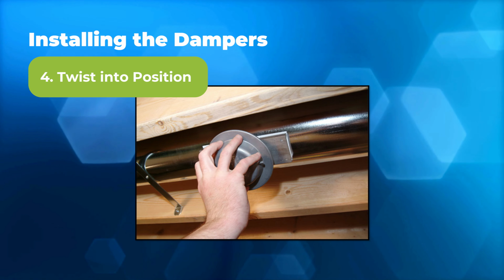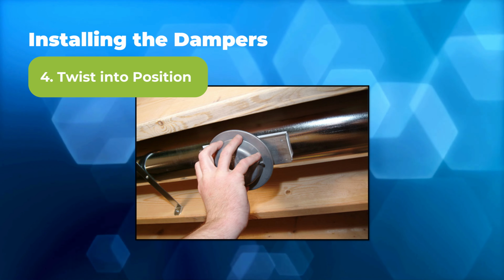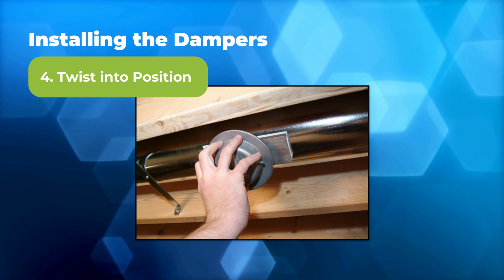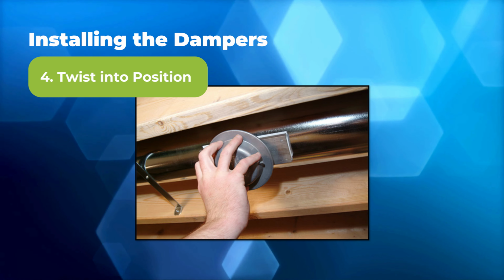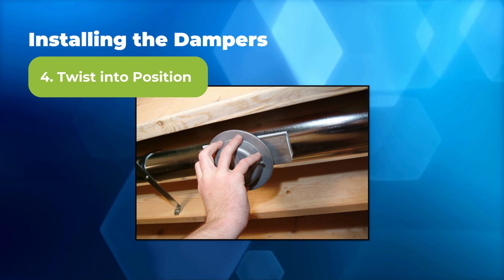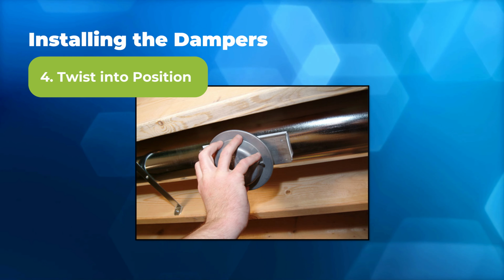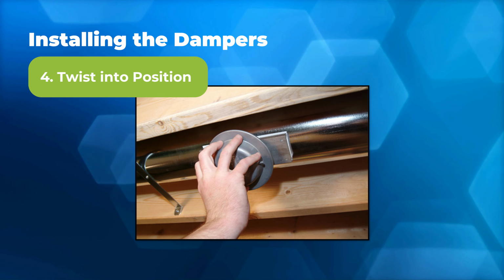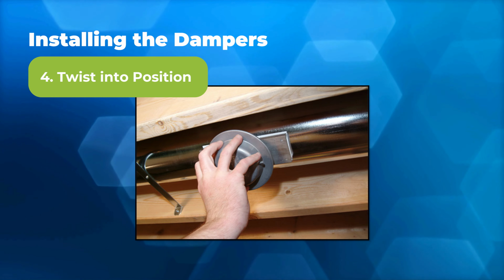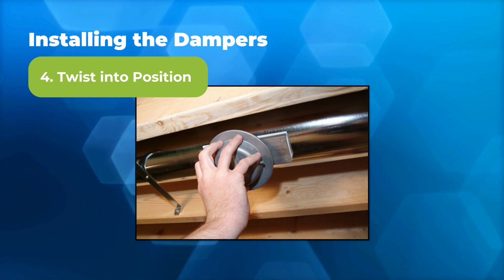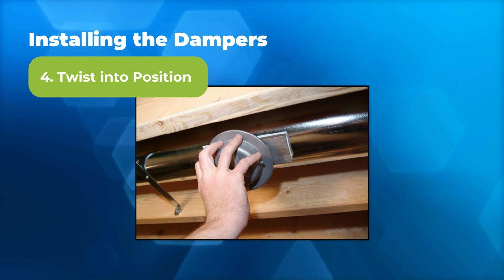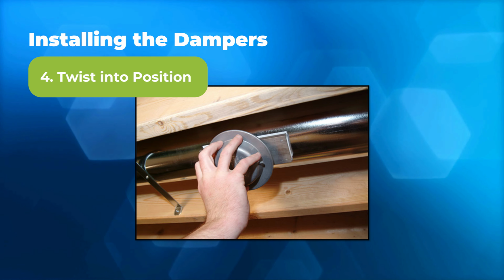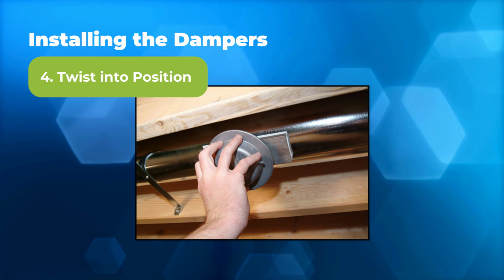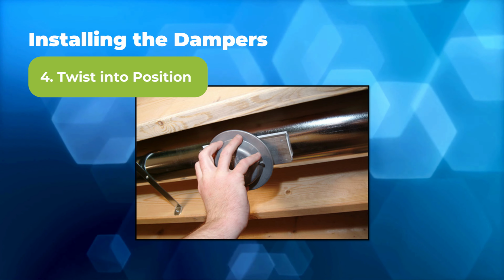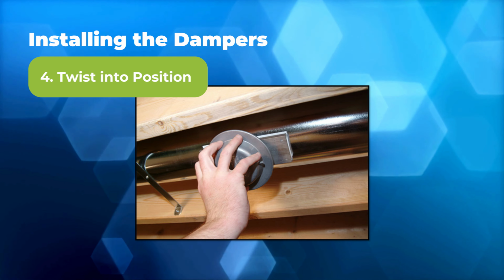The little air tube on the damper itself, so if you can see in the picture, right on the right hand by his pinky finger, there's a little nipple there, and that's where your hose will actually attach. You're always going to want that pointing towards the equipment that you have, or against the airflow if you look at it that way. That's just for a cleaner install so that your tubing all goes back to the main plenum, and then you can route that back to your panel, so it makes it a lot cleaner. If you do need to put it the opposing way, it's not going to affect the way that the damper works at all. It's just more of an aesthetics thing.